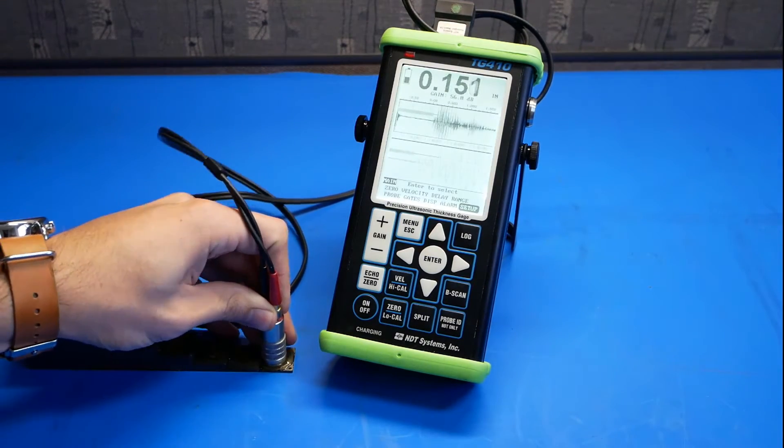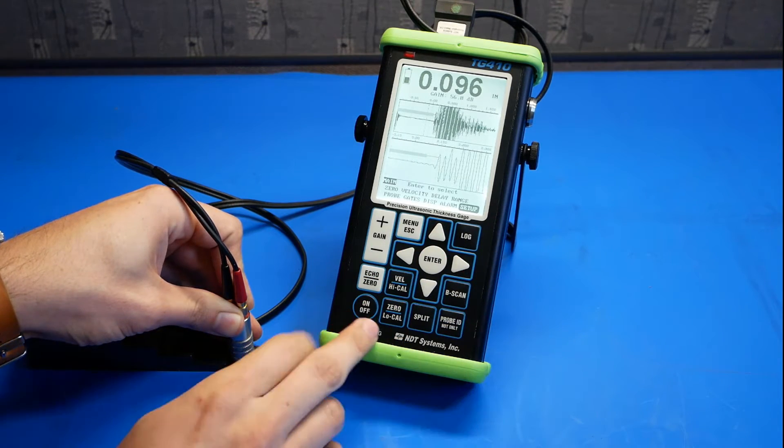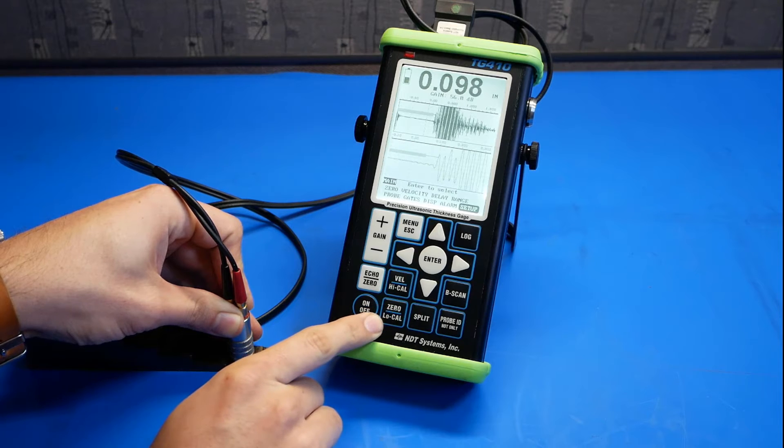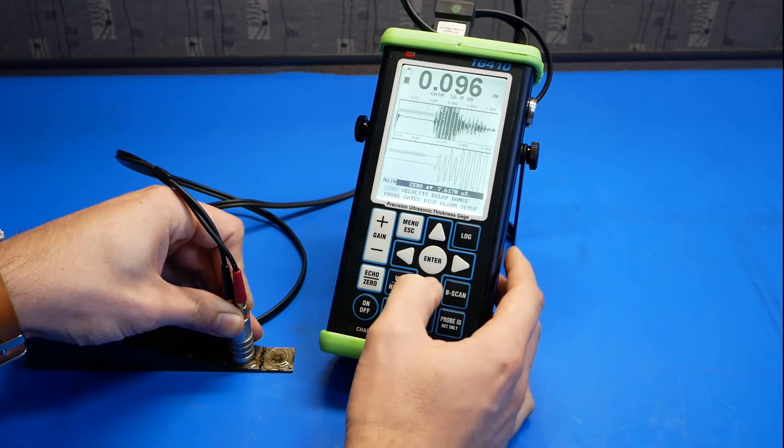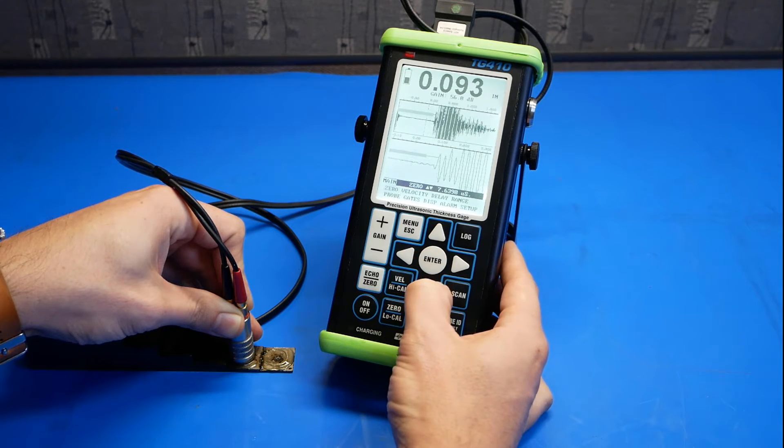Go ahead and couple your probe to the thinnest section that you're going to be measuring. In this case, it's 0.1 inches for me. Go to the zero or Lo-Cal button on the keypad. Push enter, and we'll adjust the zero until the reading on the screen matches our gauge reading.